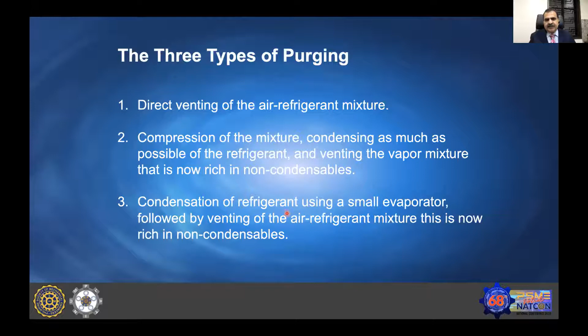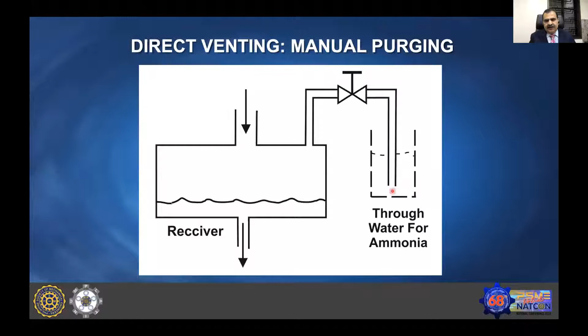Typically, in a direct venting or manual purging system, we provide a purge valve at the receiver or at the inlet of the condenser, and we manually operate this valve into a water bottle or water container. You have to take great precaution when you are doing this, because ammonia is a hazardous gas. If you are venting ammonia, you must have proper precautions. The PPE kit must be used. The valves must be properly connected. The valves on the condenser or receiver must be connected to a proper hose, and the hose must be dipped into the water bucket.